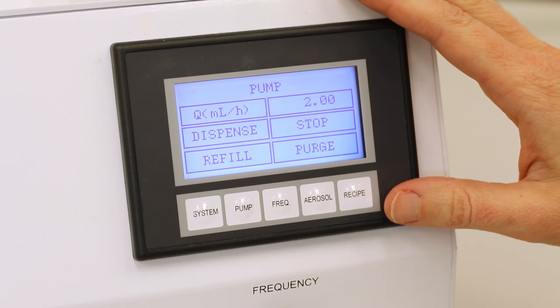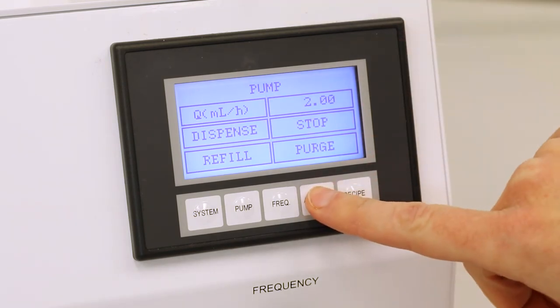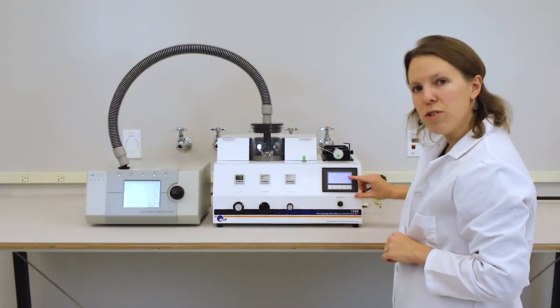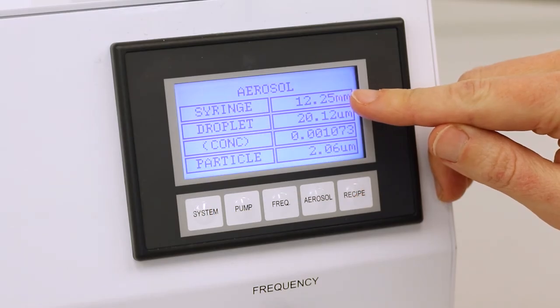Now I turn my attention to the front screen of the FMAG. I want to be sure that the syringe diameter entered into the menu is correct for the syringe I'm using.